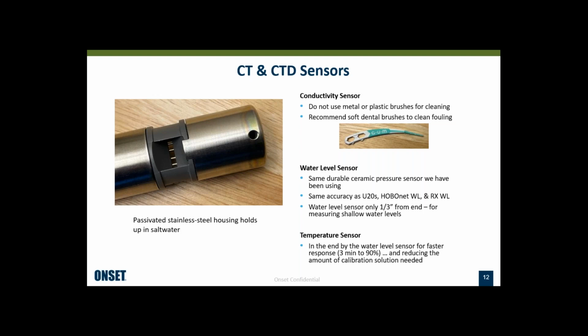And one of the things you'll notice is the end of the sensor is very flat. That's useful for using these sensors in applications where it can get very shallow. You put it so that it's pointing down, and it can sit on the bottom and measure water levels down to 1/3 of an inch from the end. So that's better than any of our other water level loggers. The temperature sensor is also in this end unit, and that's important for good temperature compensation of the pressure and the electrode readings. And it also gives just better temperature response, 3 minutes to 90% of the water temperature change, which is pretty good. It also reduces the amount of calibration solution that's needed when you're calibrating the conductivity sensors.